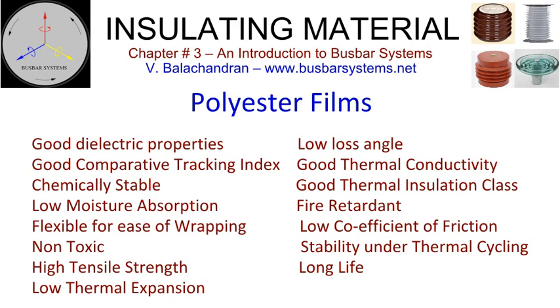Wrapping of polyester films on bus bars is highly automated. The mechanical properties vary for machine direction, MD, and transverse directions, TD. Polyester films are available in rolls of different width with or without an adhesive coat. The insulation required for a sandwich bus, busway, must have the following properties.